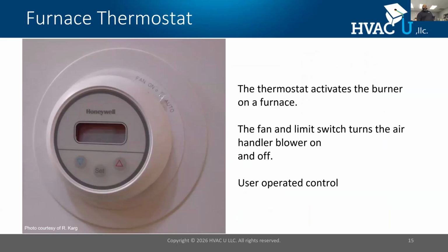Let's explain. We talked about the thermostat, the user operated control. The way your system works, it reacts to a set point and runs until the set point is satisfied. That's how your thermostat works. They have a lot of features and a lot of interconnectivity. They can be connected to other items in your home, such as a smart house, but this is the decision maker that tells the system to turn on and off. And if we don't have a good equipment size to duct process, customers may have a thermostat that's satisfied, but they still feel uncomfortable due to other factors. So the reaction is they may want to go and alter that thermostat.